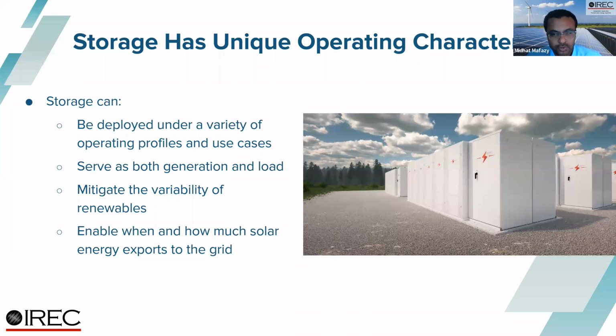It can act as a purely non-exporting resource, a full export resource, or a limited export resource that limits export to a specified magnitude. Storage may be able to limit export during periods of low demand and instead ramp up export during periods of peak demand. If properly evaluated in screens and studies, this control flexibility can better serve energy needs while also allowing more DERs to interconnect without triggering the need for upgrades.